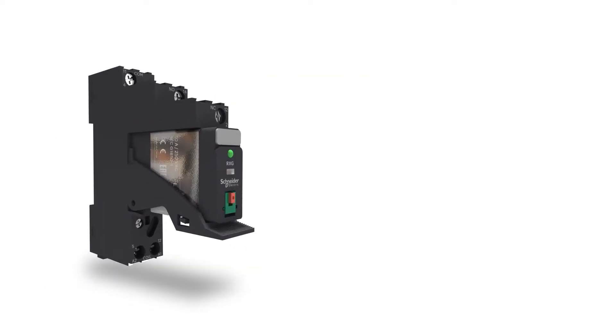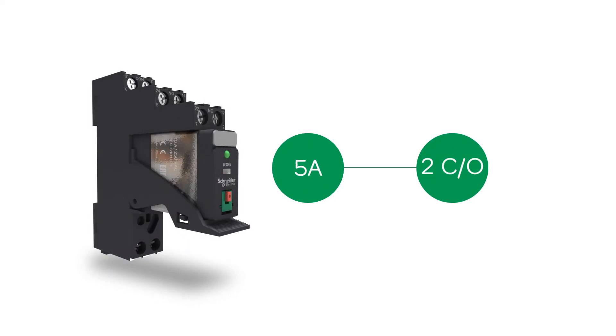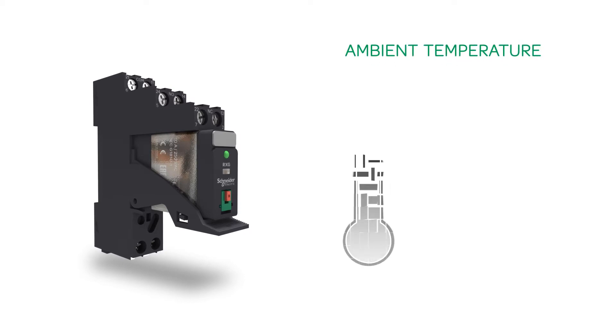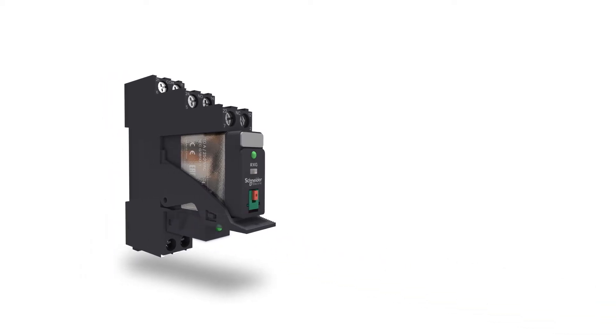The Zelio RXG interface relay range comprises of sockets, 10 amperes relays with 1 changeover contact and 5 amperes relays with 2 changeover contacts. Zelio RXG can operate at ambient temperature of negative 40 degrees Celsius to 70 degrees Celsius. It gives the highest performance among the industry players. Protection modules can also be added.